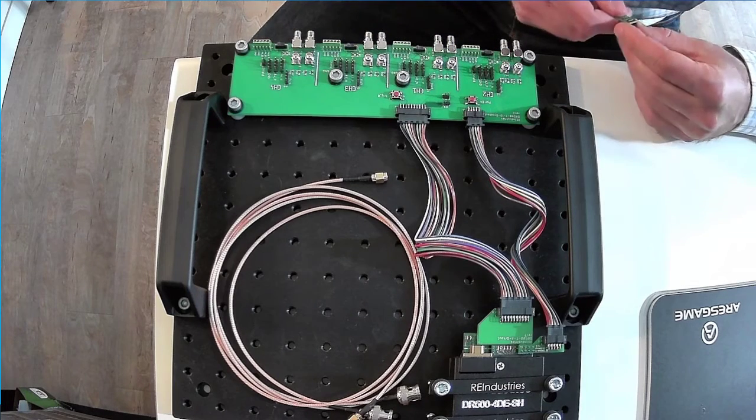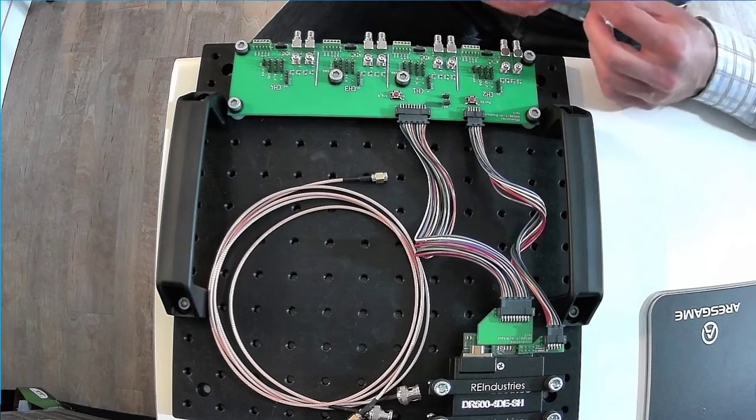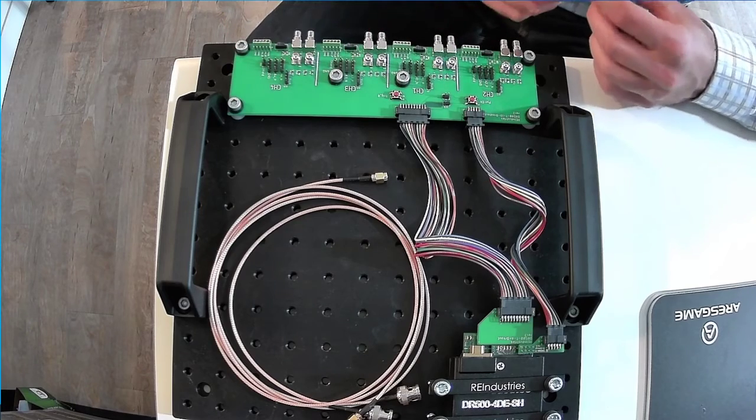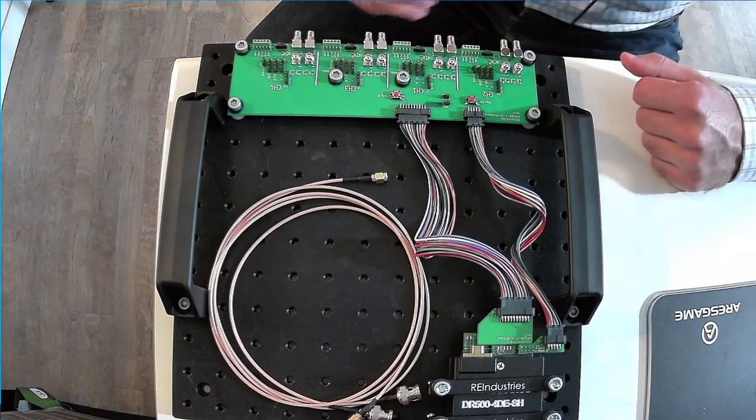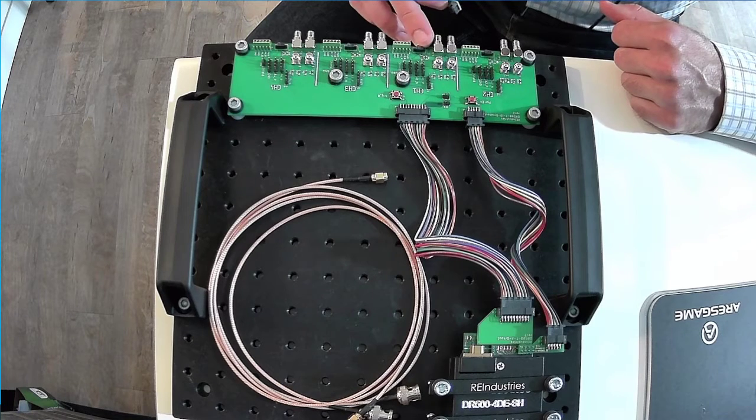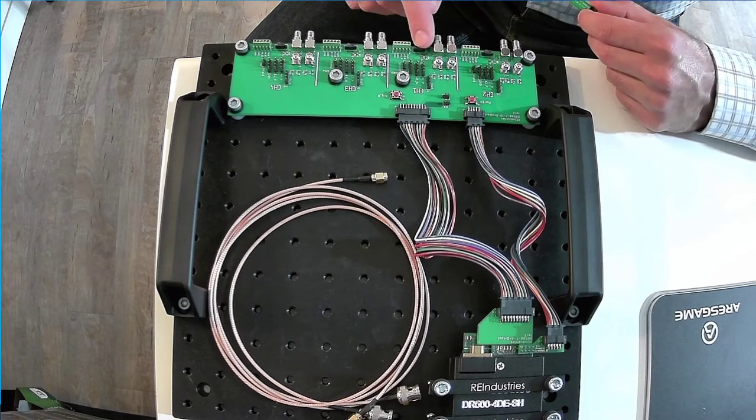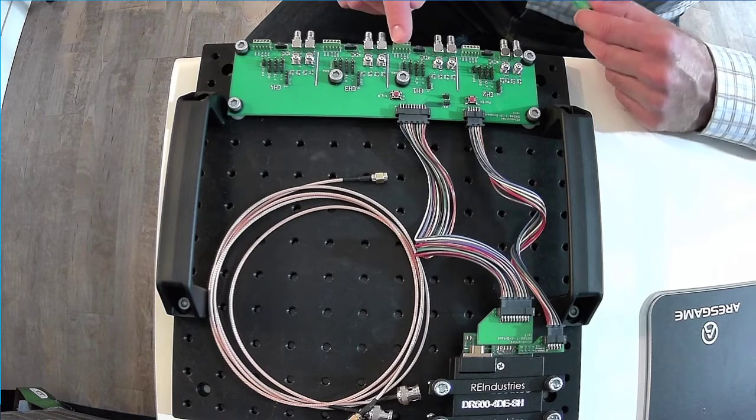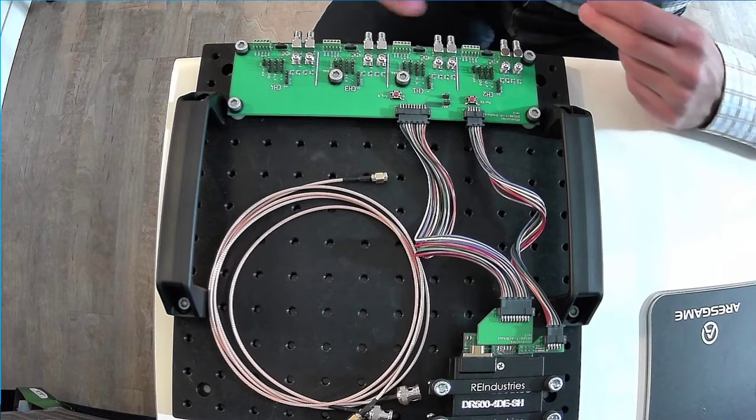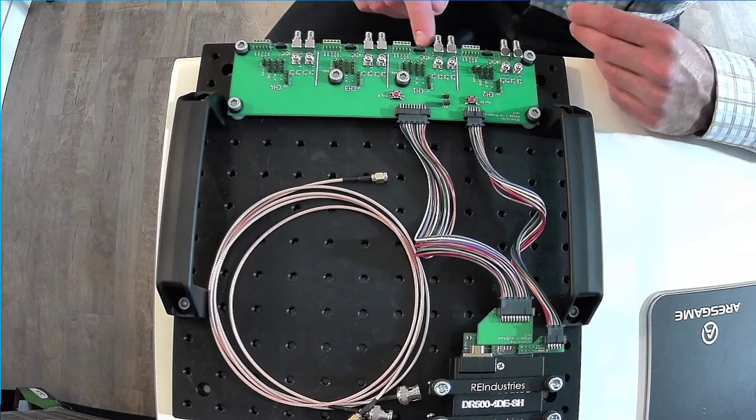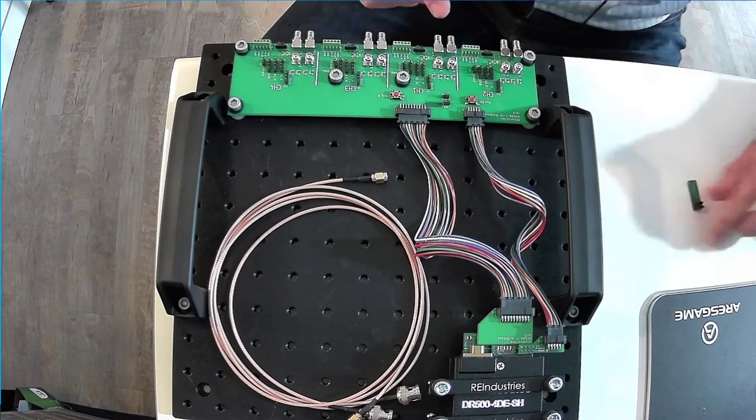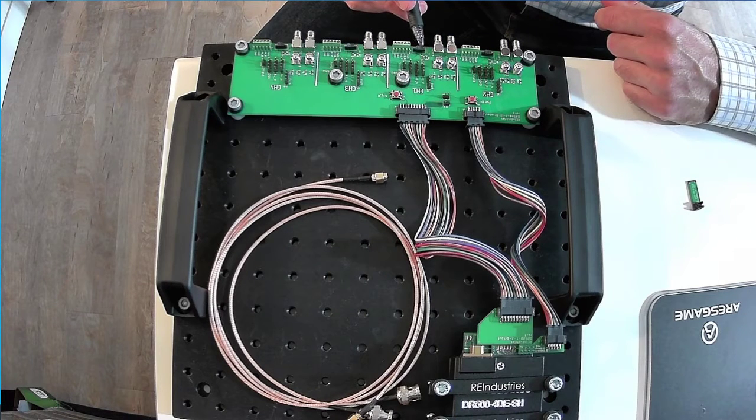So the next interface is actually a really useful interface. This is used a lot in-house as well. So this is a little micro connector that we use. We'll have high resolution images of all of this on the blog post. So feel free to find the link in the description and go check out some of these visually in more detail with high resolution images. But we've got a micro connector here. Very small. It's eight pins. And this micro connector and this terminal block, both of these connectors carry standard accelerometer and other sensor signals that consist of sensor biasing or V bias or the excitation voltage, sometimes called for an accelerometer. A ground for that, the positive and negative differential signals, and then the shield. So there's five signals. And in the silkscreen, the terminal block's labeled. It would be in the user's manual.